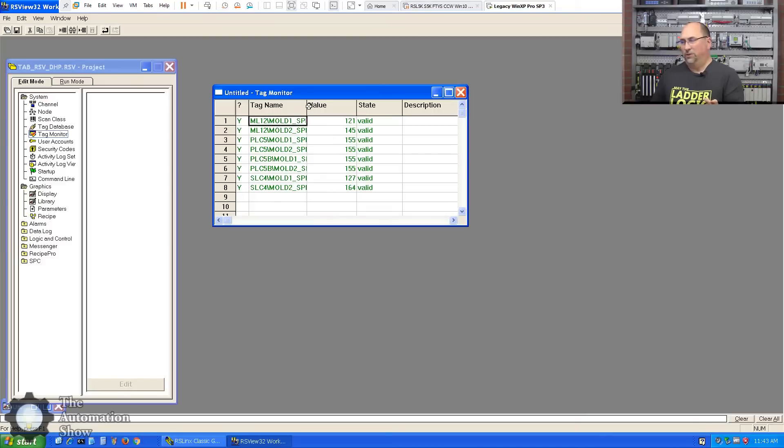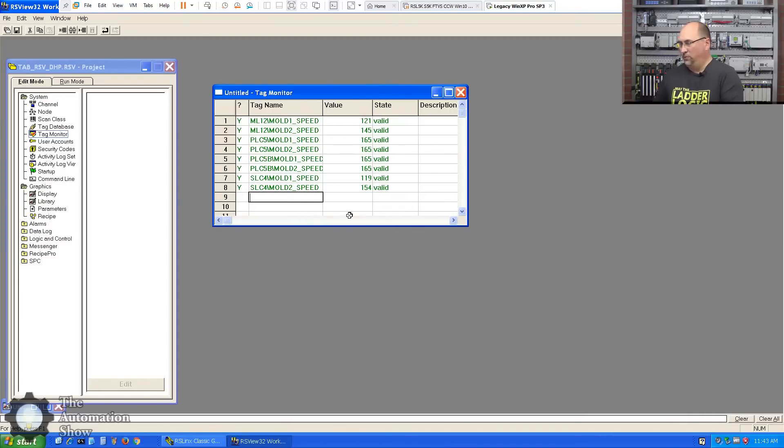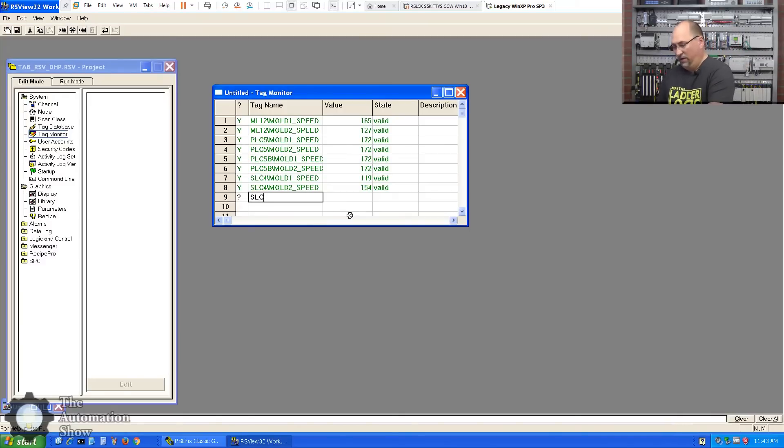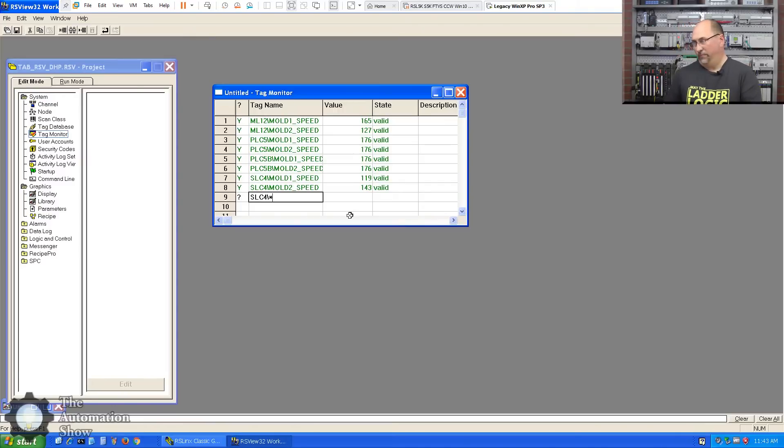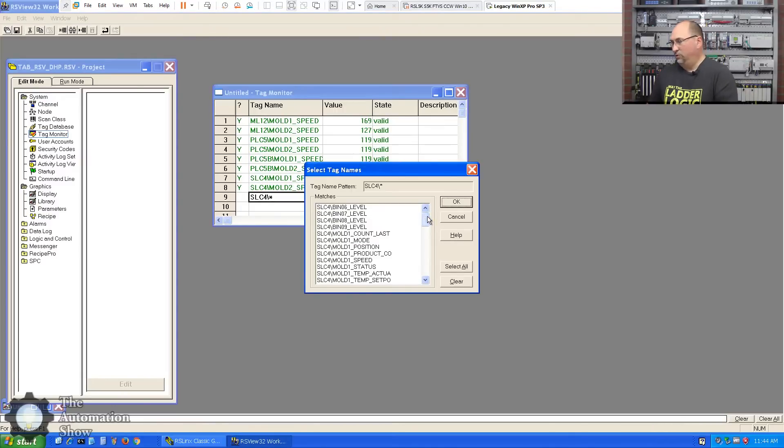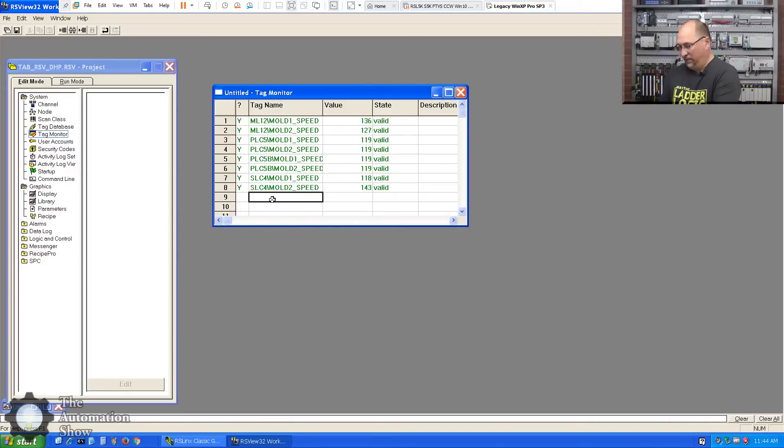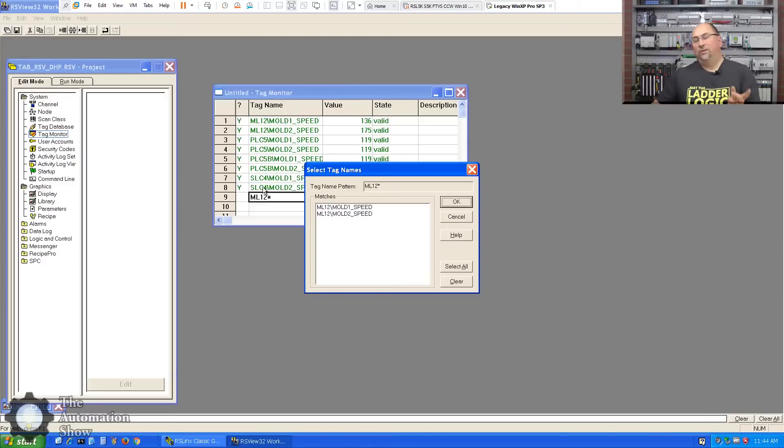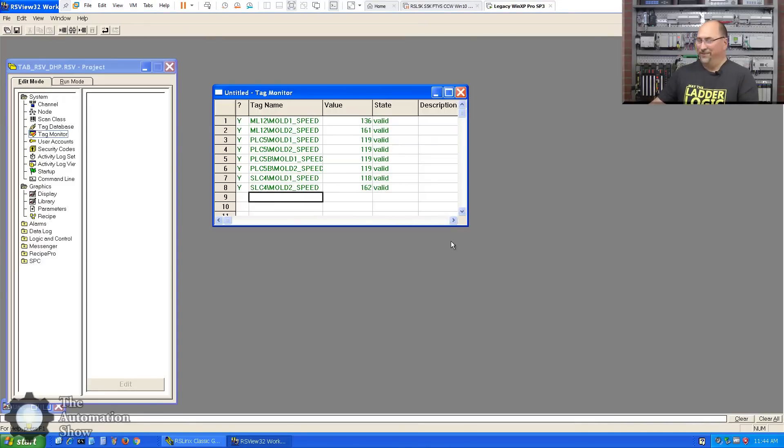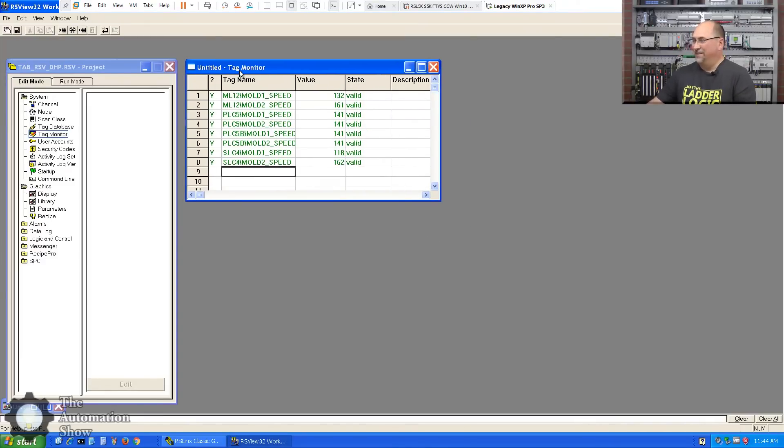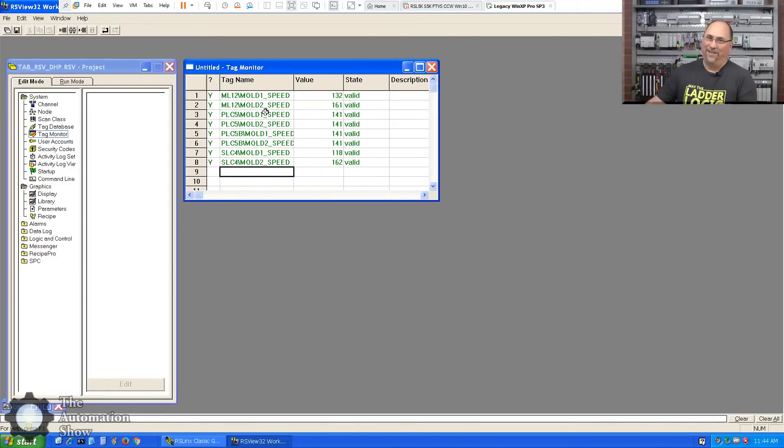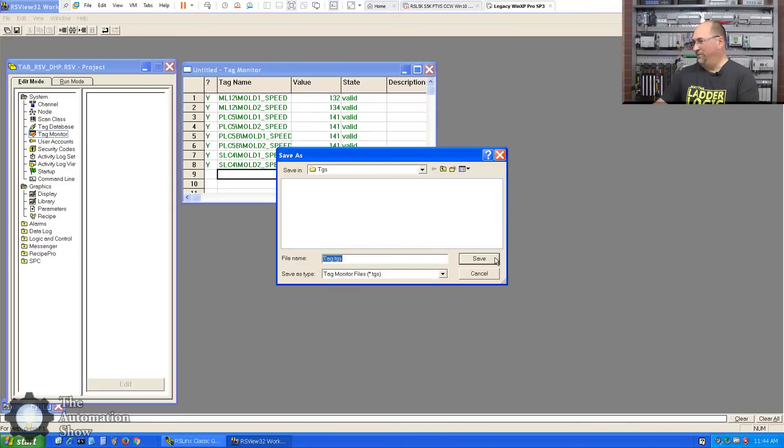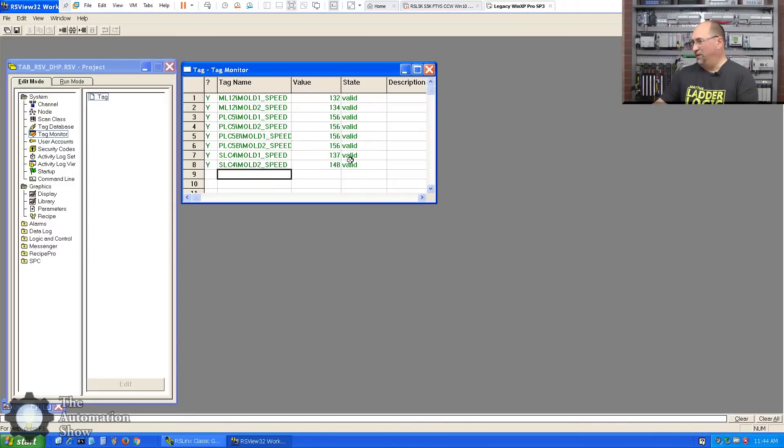Okay, now here's a trick that a lot of people don't know. Not only can you press the asterisk to bring up the tag browser, but the downside is it only shows you 100 tags. Now that's not a problem for here. I got these two guys right? And let's see, I can do the one from the PLC5, one and two. And then let's see, the SLC4. What would have happened if I had more than 100 tags? How would I get those in the browser? Well, the way you would do it is first you would type in like the beginning. And this is like one of the reasons why it's great to have tag folders. So if I just wanted to see the SLC4 tags right, I could do that, and now it shows me 100 tags from the SLC4 folder. Same thing if I wanted to see all the tags for let's say ML12 asterisk.